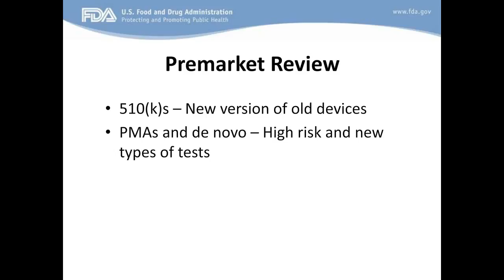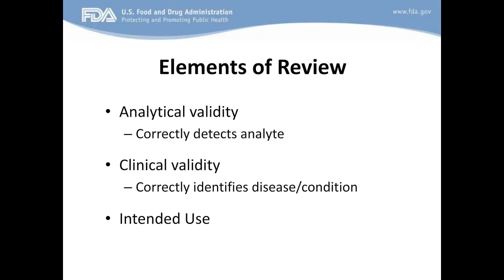What are the elements of review? The elements of review for 510(k)s and PMAs are, at least in general, similar. That is, we look at whether a test is analytically valid. That is, does it correctly detect the analyte, or what it is believed to detect, the measurement if you like, and does it detect it correctly? And clinical validity, that is, does it correctly identify the disease condition? What is the link between the analyte that you are detecting and the disease condition? And in general, and very important for all of these, everything that we review is driven by the intended use of the test. The intended use of the test is crucial for determining what its analytical validity should be and what its clinical validity should be.